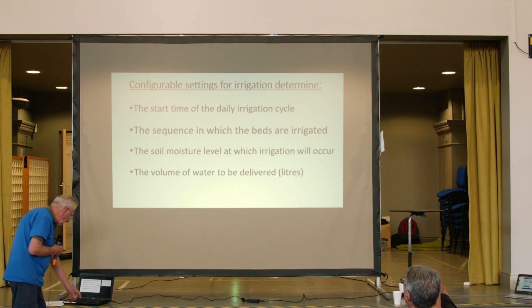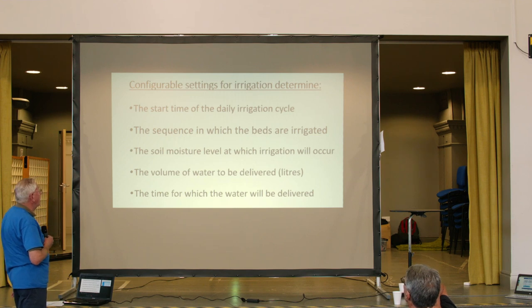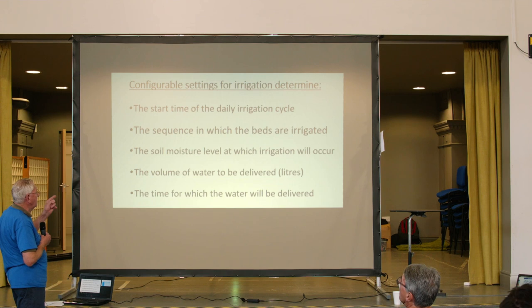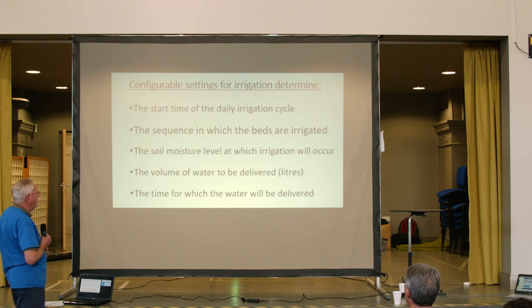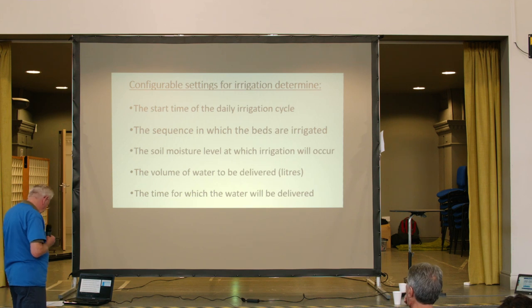You can also configure the time for which the water will be delivered, which is really a backup to the volume measurement. Because if the flow sensor fails, you don't want to be delivering water forever. So that time setting pretty well matches the volume delivered anyway.